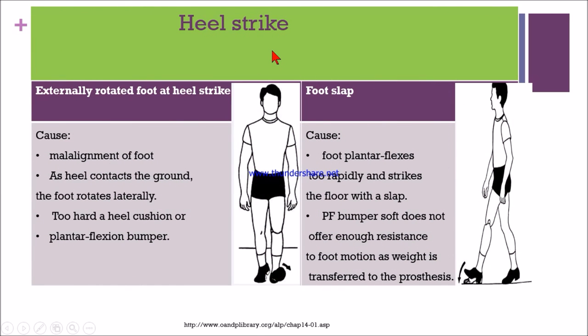Next is heel strike in transfemoral gait deviation. There are two gait deviations at heel strike: external rotation of the limb, or foot slap at heel strike. If the foot is malaligned, as the heel contacts the ground the foot rotates laterally. If there is a too-hard heel cushion, the leg will go into external rotation. If the plantar flexor bumper is too hard, the knee will also go into external rotation.